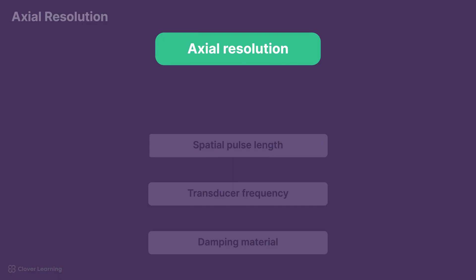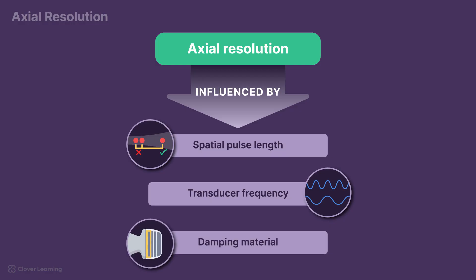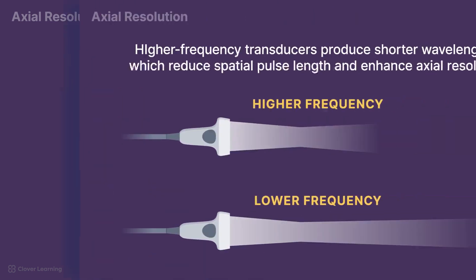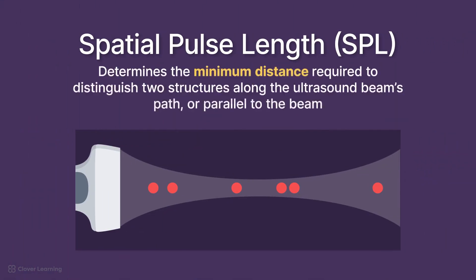Axial resolution is influenced by spatial pulse length, transducer frequency, and damping material. Spatial pulse length directly affects axial resolution, as shorter spatial pulse length improves resolution by reducing the overlap of echoes from adjacent structures. Higher frequency transducers produce shorter wavelengths, which reduce spatial pulse length, or SPL, and enhance axial resolution.